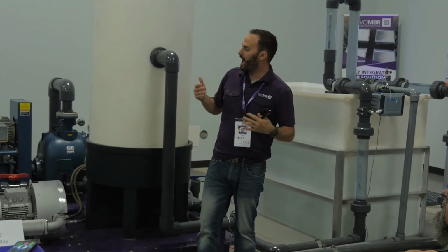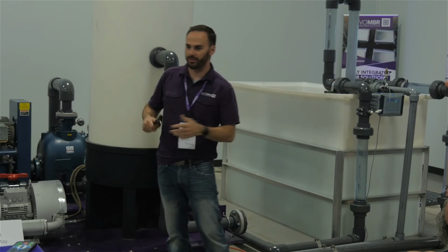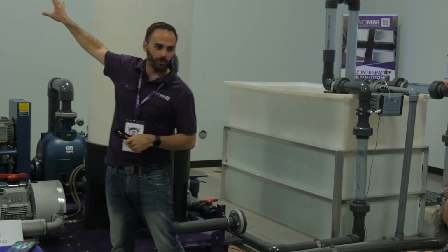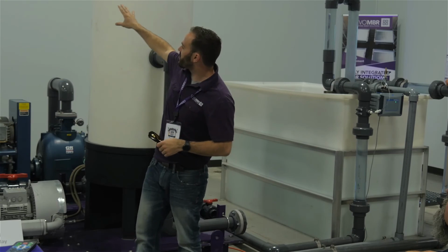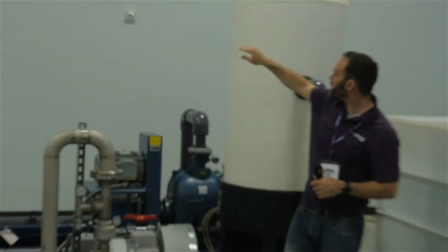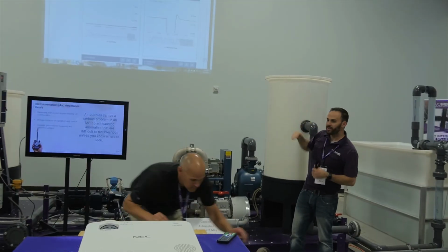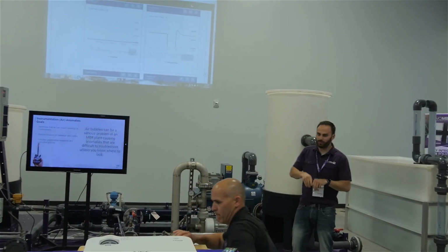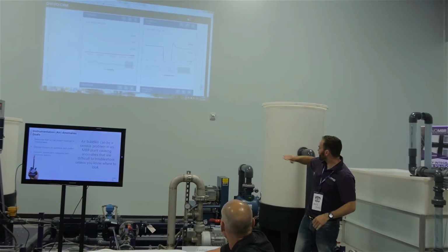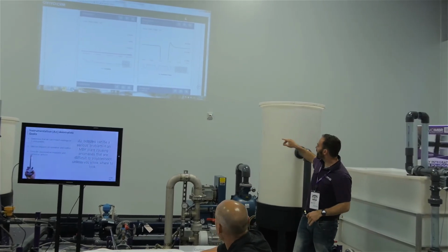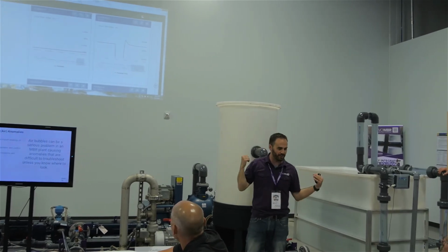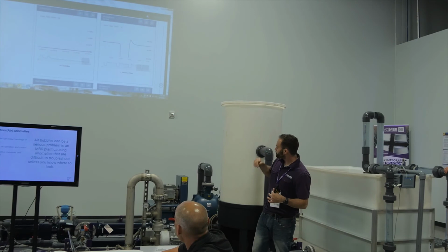So, if we look up here at Water Expert, you guys can see that we're watching permeate flow. Again, this just happened a few seconds ago. If we look at that permeate flow, it does what we like to see. It just spikes up a little bit, and then it finds that flow, and it just is a stable, straight line. Turbidity is the same thing. It's a very low turbidity number. It's clean water, obviously. But it's just a stable, very low, straight line.